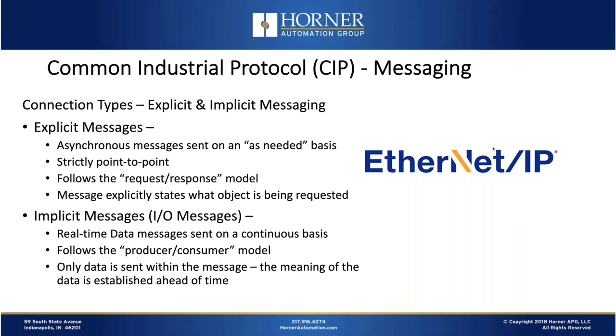The two most common connection and messaging types in CIP are explicit messages and implicit messages. Explicit messages are asynchronous in nature — they're only sent on an as-needed basis, such as tuning parameters for a PID loop. They're strictly point-to-point, one to one, and follow the request-and-response model. They're called explicit messages because the message itself explicitly states the object and service being requested — all that information is contained in the message when the request is made.